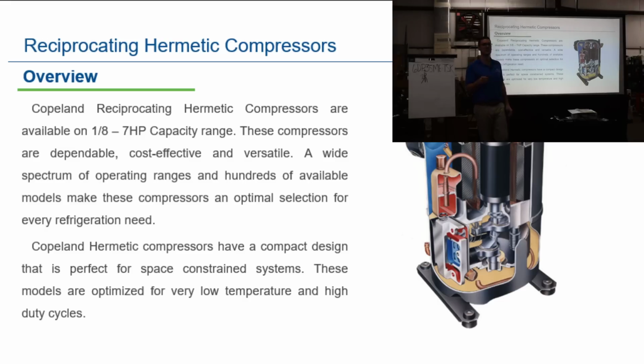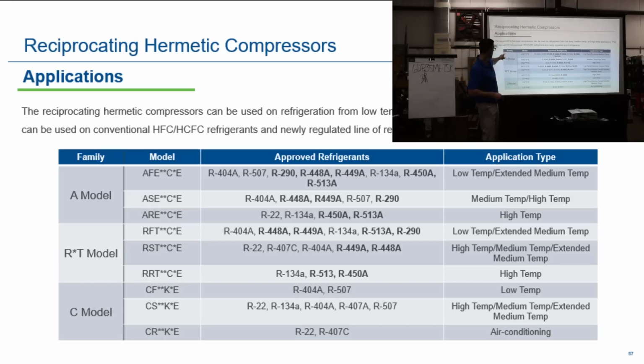What was the question again? Why would we put the discharge through the oil? Be cool. Not cool, opposite. Warm to heat the oil, and if any refrigerant in there, to boil any refrigerant off. We have different models, A, R, and C. As you can see, I got them all highlighted in bold, all the new refrigerants that these compressors can do. And then on the end, like low temp, extended medium, or high temp.